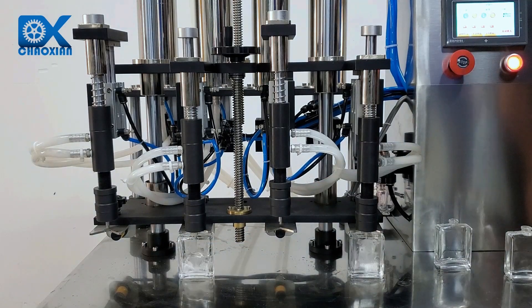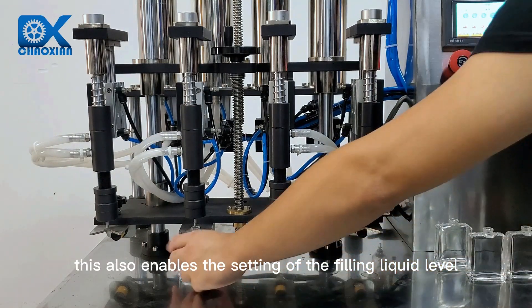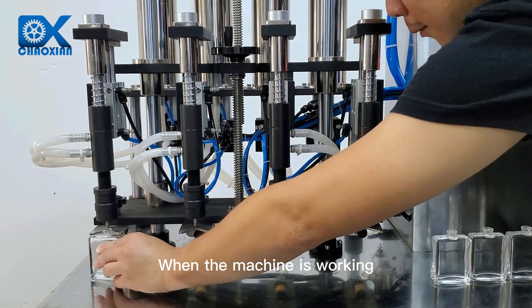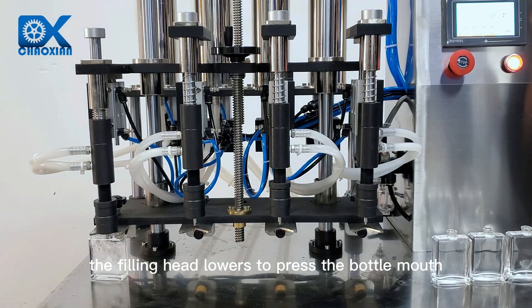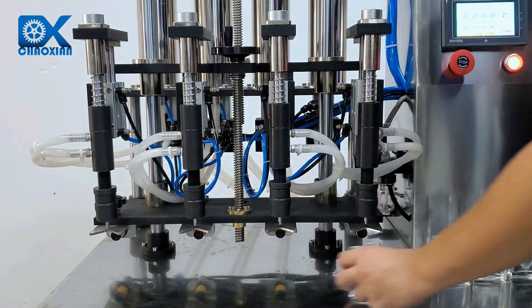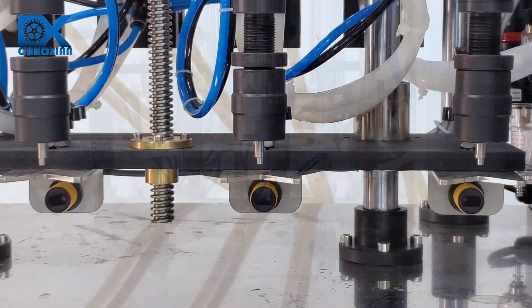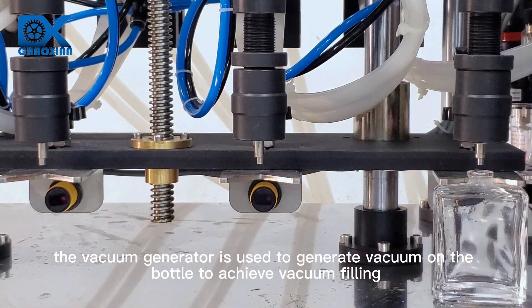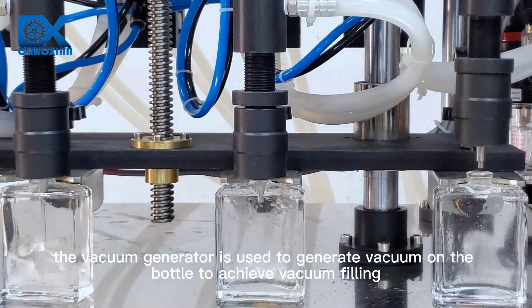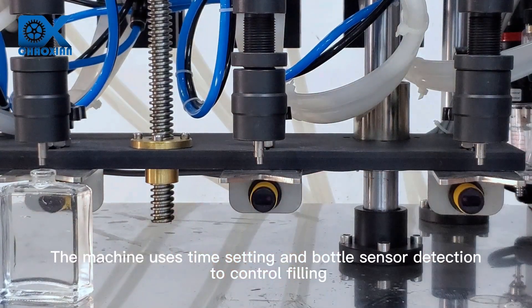This also enables the setting of the filling liquid level. When the machine is working, the filling head lowers to press the bottle mouth and achieves a sealing effect on the bottle. The vacuum generator is used to generate vacuum on the bottle to achieve vacuum filling. The machine uses time setting and bottle sensor detection to control filling.